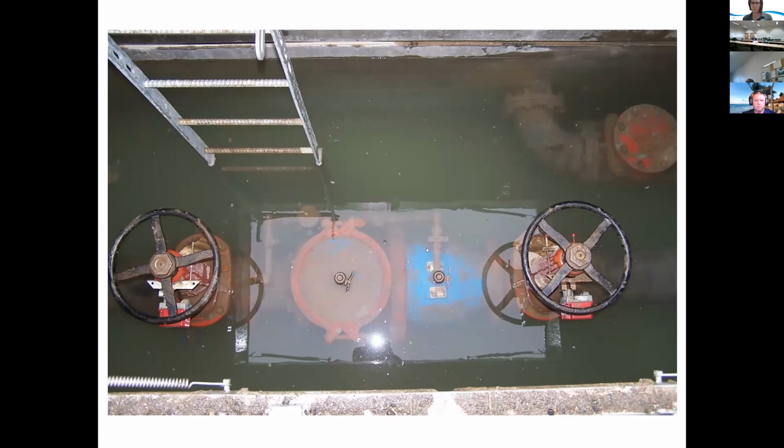BMI, Backflow Management Inc., had a video at one time where they did a little experiment and submerged a double check valve assembly in blue water. Then they ran water through the backflow assembly, and you saw blue water coming out the end because of slight leakage through the test cocks.